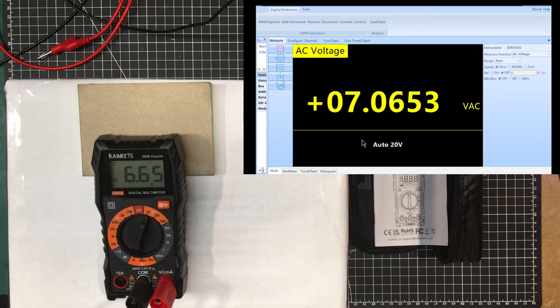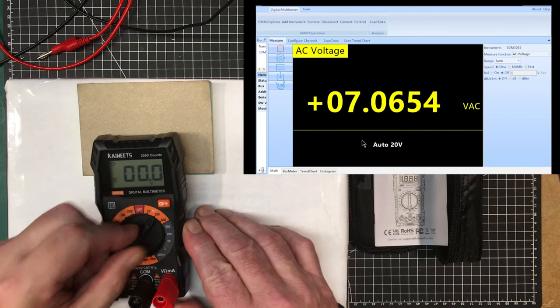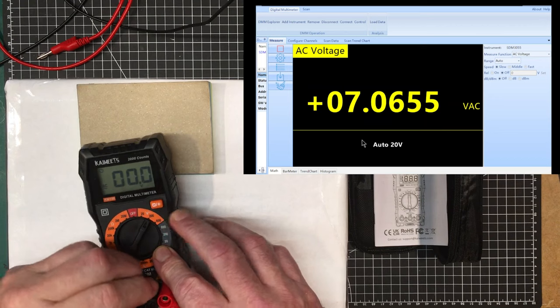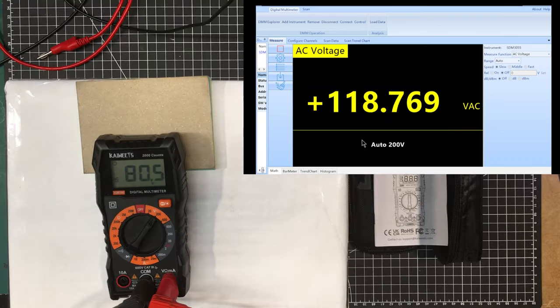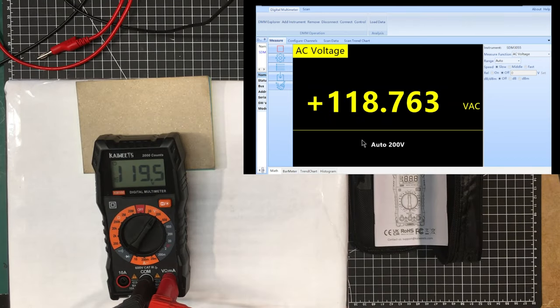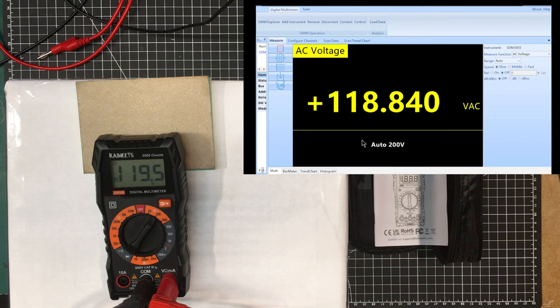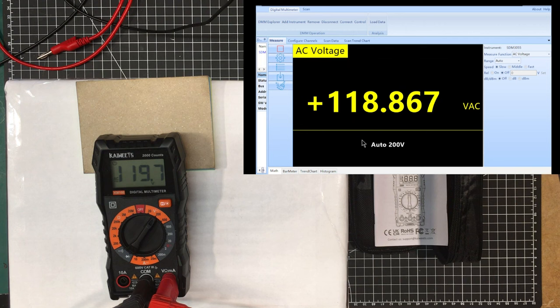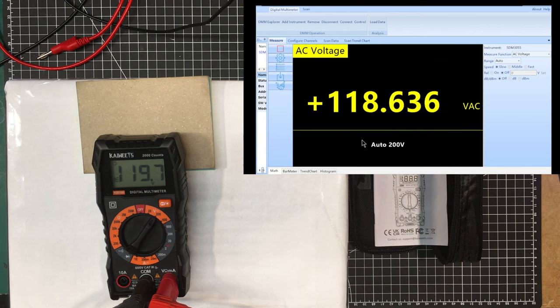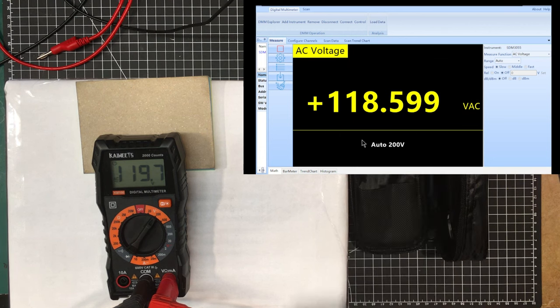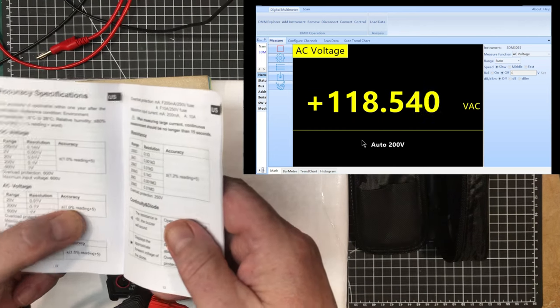Let's see how it measures the mains on the 200 volt range here. It's reading 119.5 and the Siglent is reading 118.7, in that neck of the woods 118.8. So it's off by one volt which is well within one percent and five count. I don't think AC is supposed to be that good. What's the AC spec? Oh yes, one percent plus five counts there on the AC, so we're just within that. That's good enough.